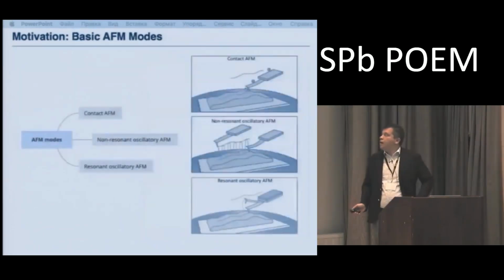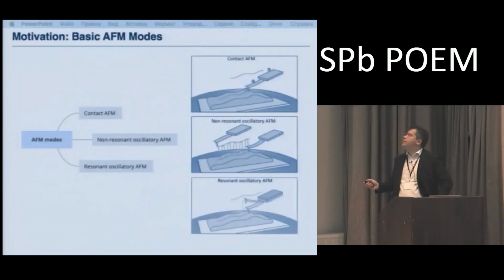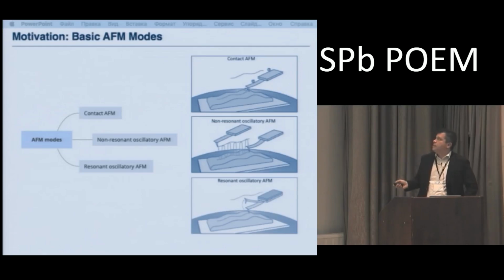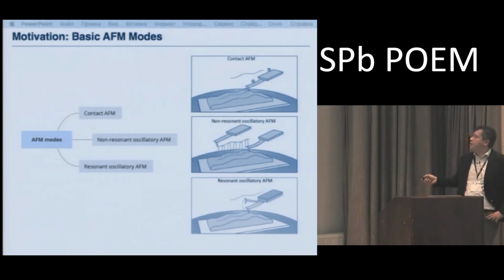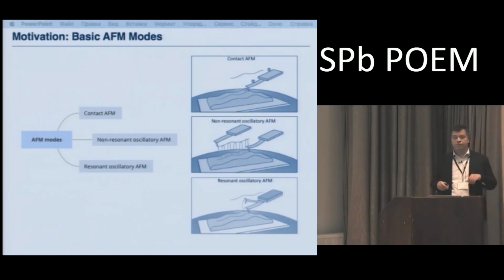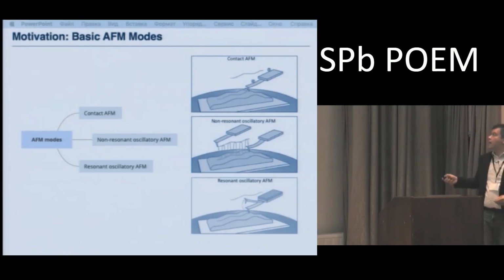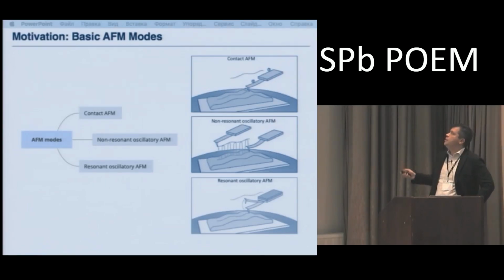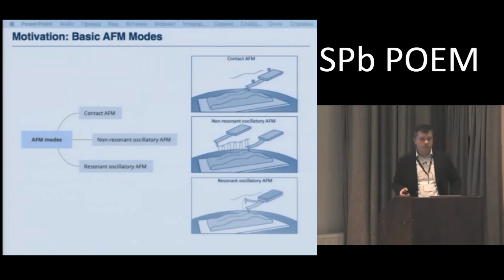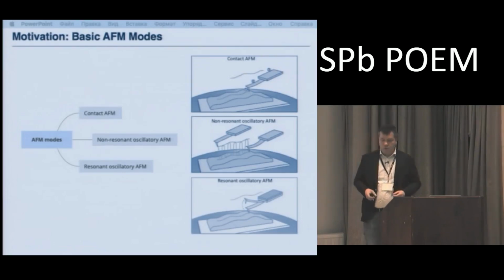The whole set of AFM modes can be split into three groups. The contact mode, where the cantilever is in constant contact with the sample. The so-called tapping mode, or resonant oscillatory AFM, or semi-contact mode in the Russian language, where the cantilever oscillates near its resonant frequency, on the order of 100 kilohertz. And another group of modes is non-resonant oscillatory AFM, where either the tip of the probe or the sample oscillates at a frequency much lower than the resonance, on the order of 1 kilohertz.